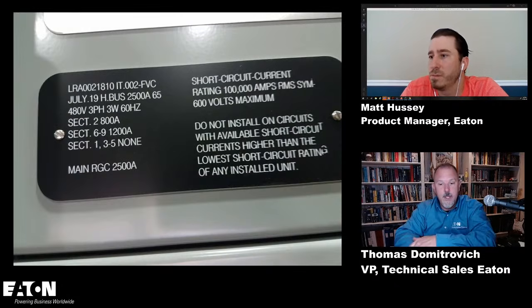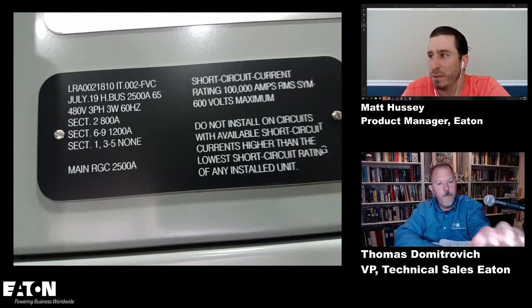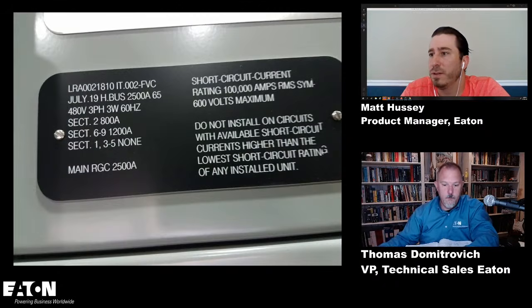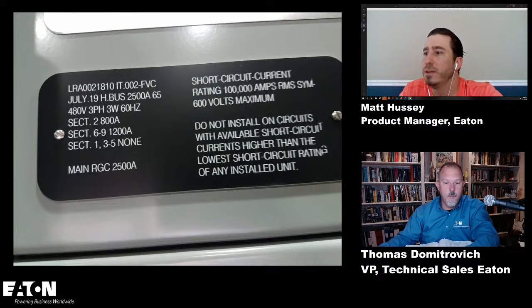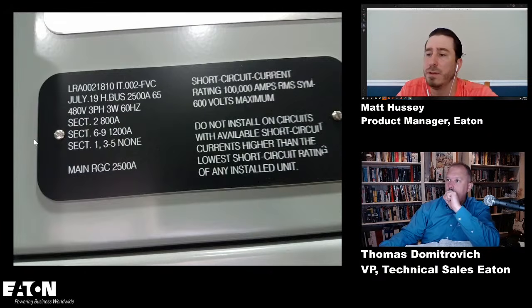Okay. So really, you could have a contactor that has a 10 kA rating, or maybe a circuit breaker that has less, but if it is utilized in a combination, it might actually obtain that 100 kA. Okay. All right. And then is there anything else on this label that's important to us?